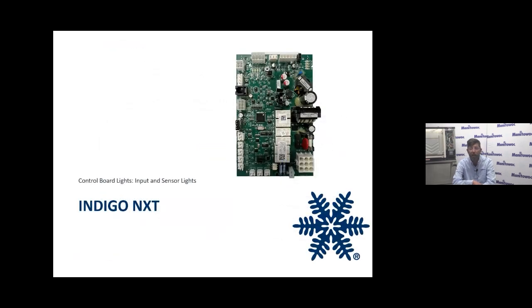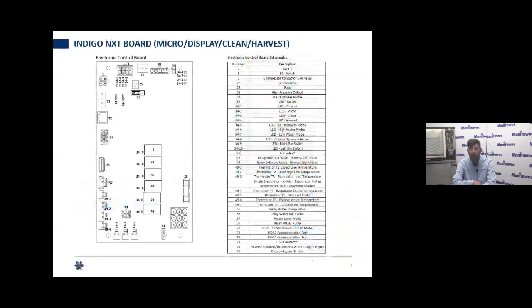All right, we're going to talk about the Indigo NXT control board lights. We're going to start with the inputs and the sensor lights at the top right-hand side of the board: the micro, display, clean, and harvest lights. That's assuming this is not an ice beverage unit. On 22-inch, 30-inch, and 48-inch machines, whether air-cooled, water-cooled, traditional or remote, or a quiet cuber that is not an ice beverage unit, the board will stand up and down. On ice beverage units, they sit sideways or horizontal, so we're going to go from the perspective of vertical. They're going to be up here, 34-1, -2, -3, and -4: the display, the micro light, the clean, and the harvest light.